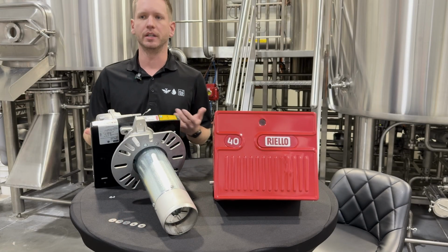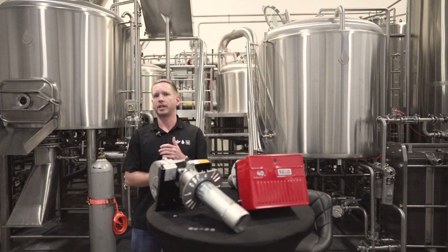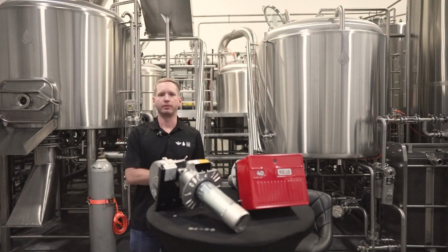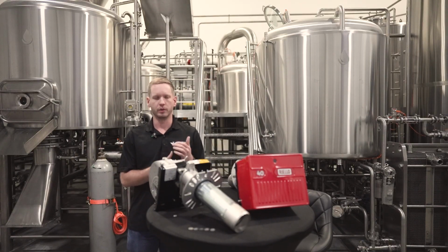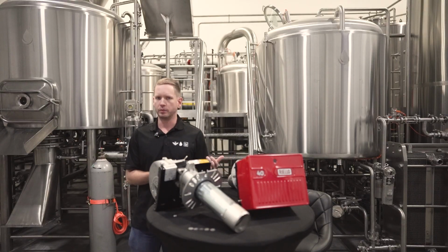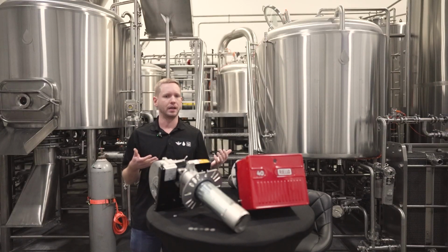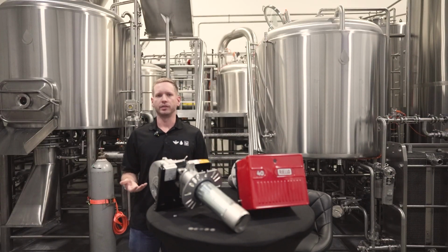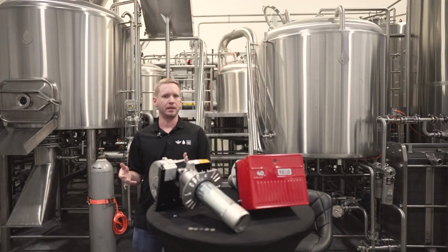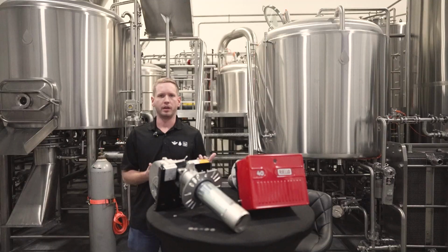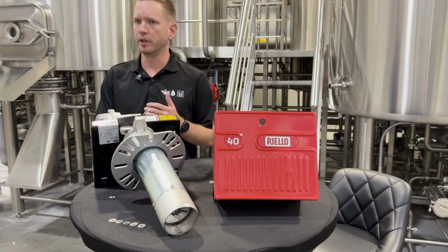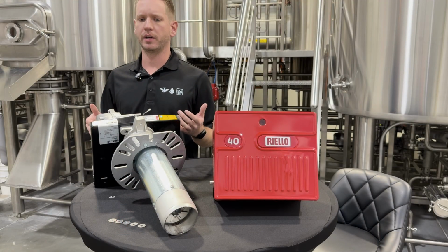First thing, if you are having an issue with your burner, is to double check that your main gas header pressure and your manifold pressure off of the control valve are at the recommended settings for your burner. That's going to be found in your Riello manual. Again, that is the main header pressure, the gas pressure coming in from your natural gas main line, from your meter, and then also the manifold pressure off that gas train following the main control valve on that burner train. So that's the first thing you want to do. Get a gas tech out there, make sure that's firing appropriately.